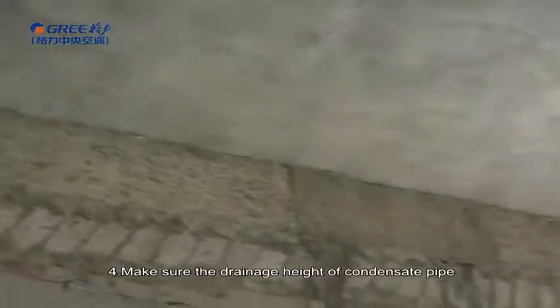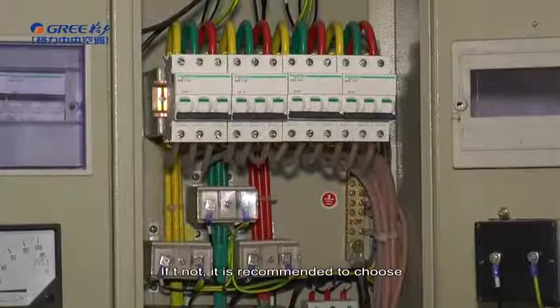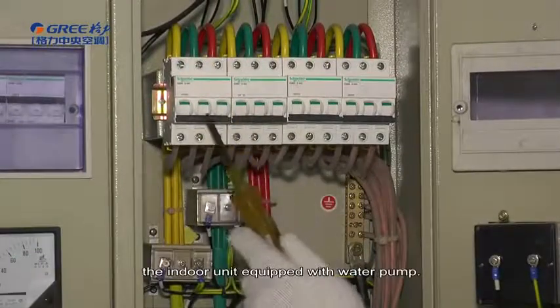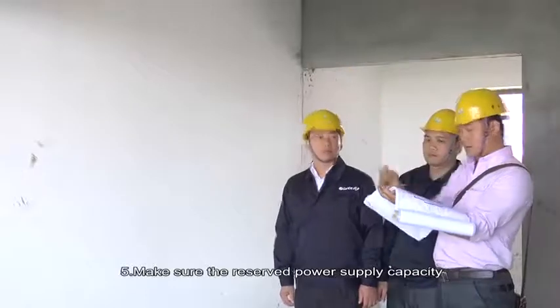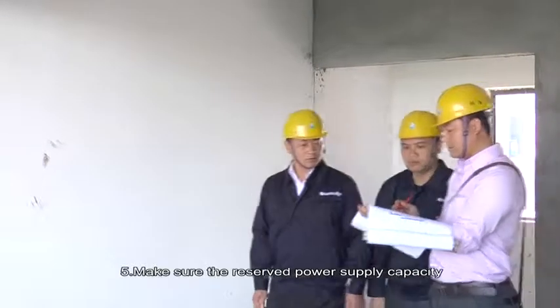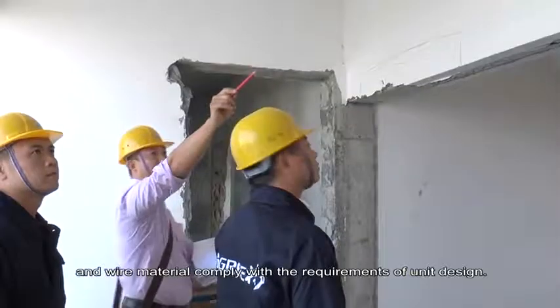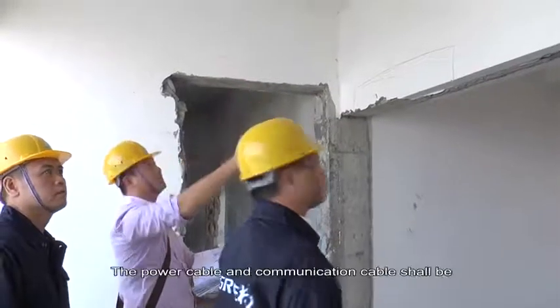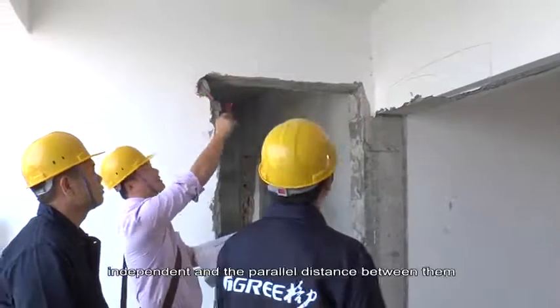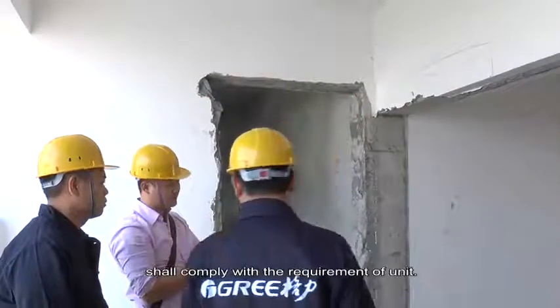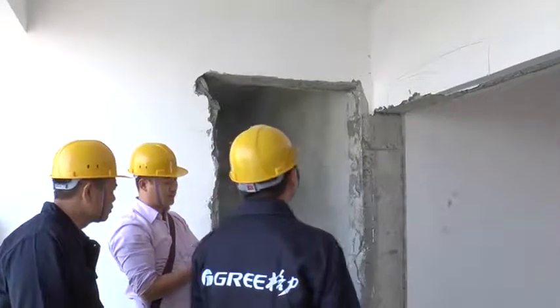Fourth, make sure the drainage height of condensate pipe is sufficient. If not, it is recommended to choose the indoor unit equipped with water pump. Fifth, make sure the reserve power supply capacity and wire material comply with the requirement of the unit design. The power cable and communication cable shall be independent, and the parallel distance between them shall comply with the requirement of unit.